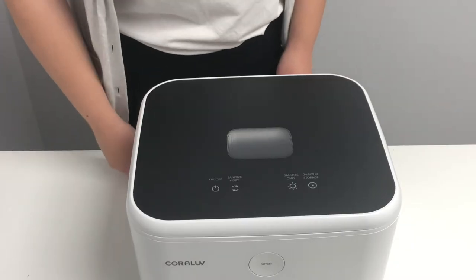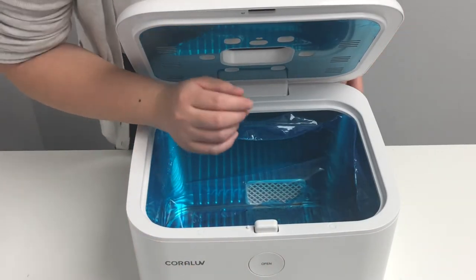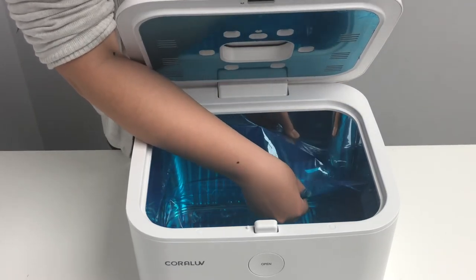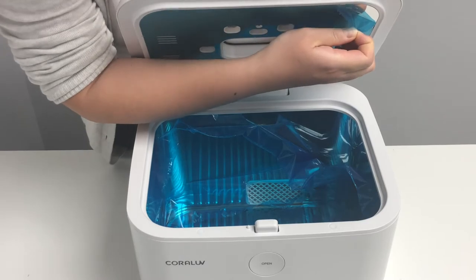To open the Coral UV 2, you press the front button and the lid will open. You're going to see plastic wrapping inside. What you need to do is take one side of the plastic wrapping and peel it off like this. And you do the same from the top — you pick one side and peel it off. It should come off super easily.